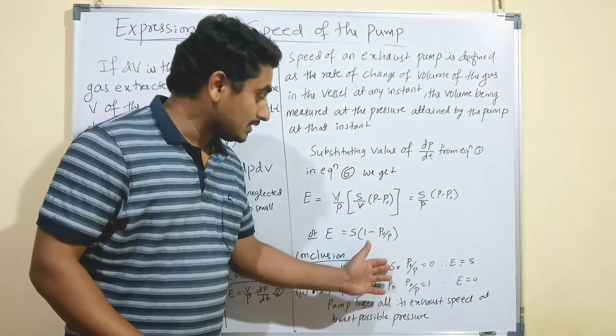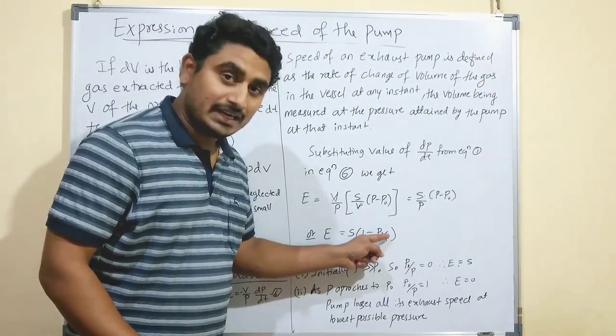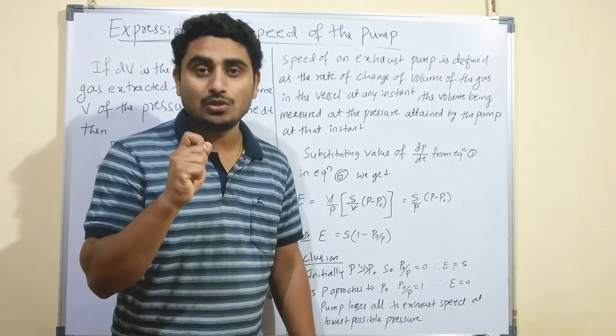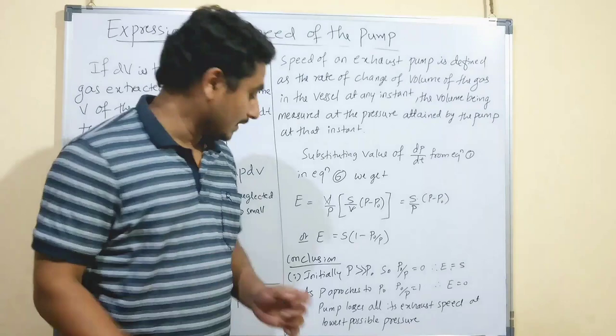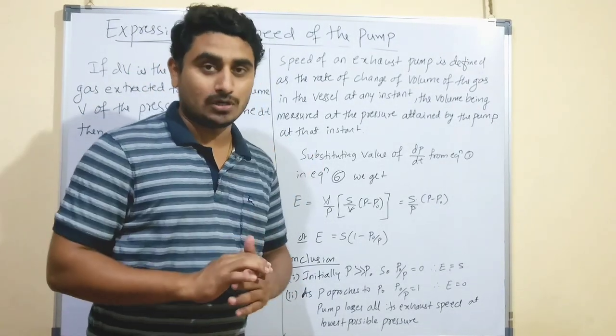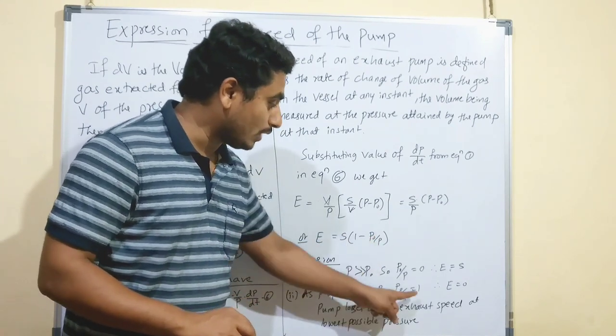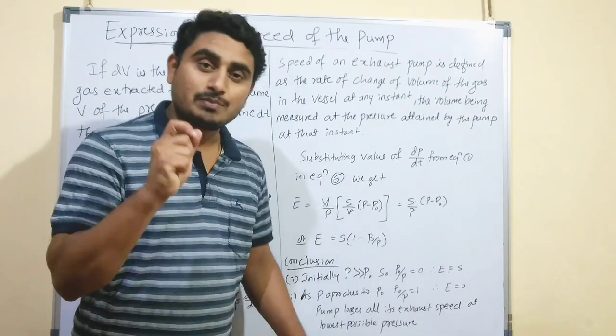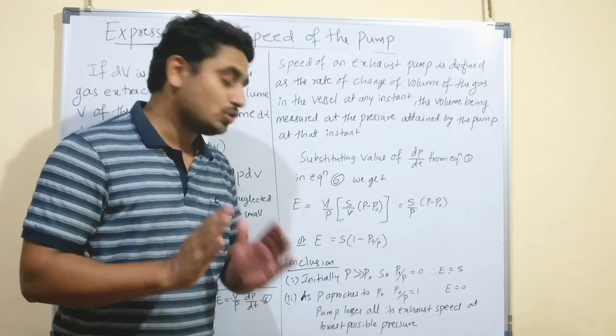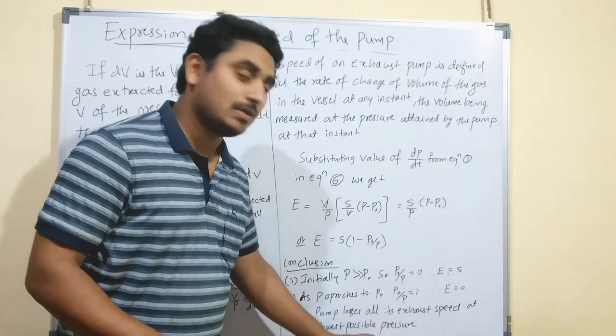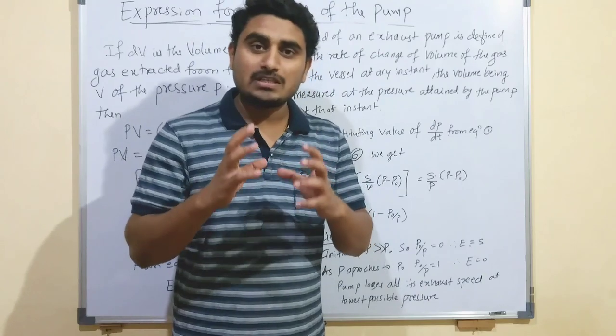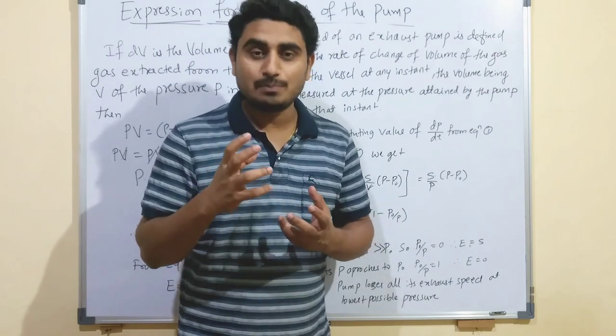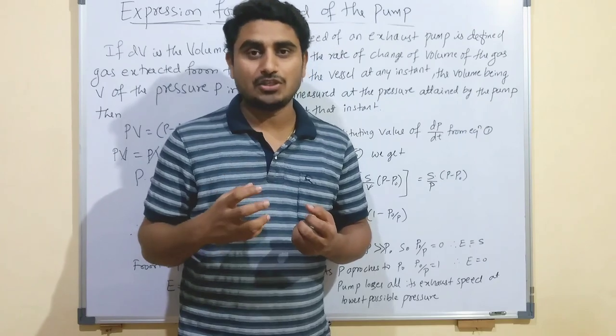Two conclusions follow. First, when P is very much greater than P0, the term P0/P approaches 0, so E = S: the intrinsic speed equals the exhaust speed of the pump. Second, as P approaches P0, the term (1 − P0/P) approaches 0, so E = 0: the pump loses all its exhaust speed at the lowest possible pressure. The pump must therefore be designed to produce high vacuum while maintaining high exhaust speed at a given pressure.